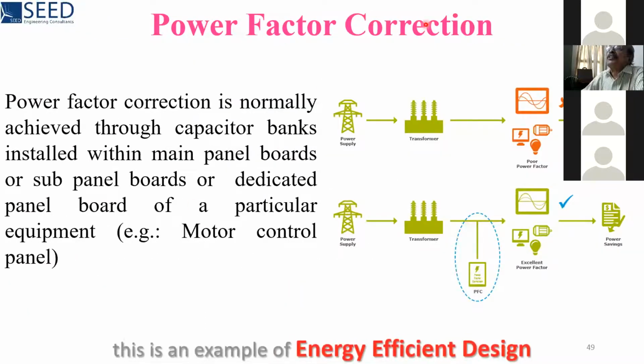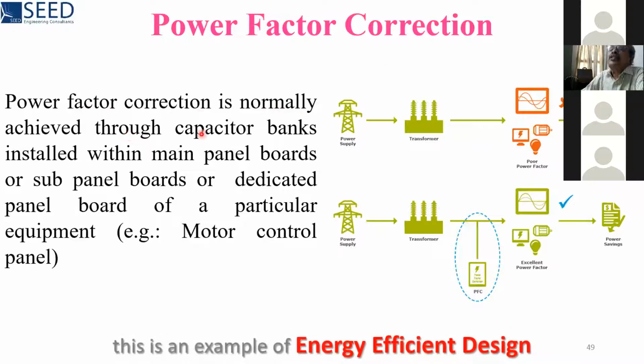See, power factor correction. Power factor correction is normally achieved through capacitor banks installed within the main panel boards or sub-panel boards or a dedicated panel board for a particular equipment, for example, a motor control panel. So an installation without power factor correction is not recommended because you are going to have increased power cost. Your electricity bill will go up. But an installation with power factor correction is acceptable because your electricity cost is going down. There is going to be a saving.